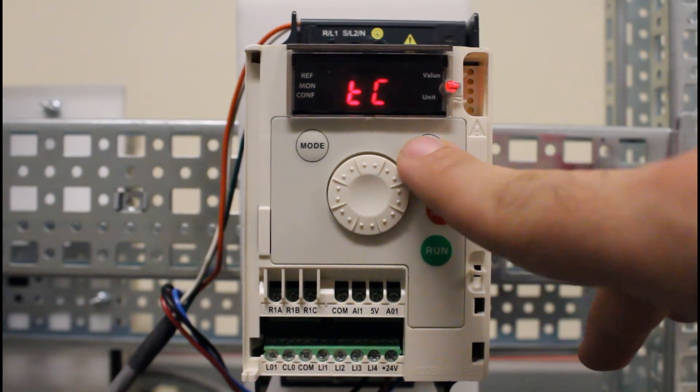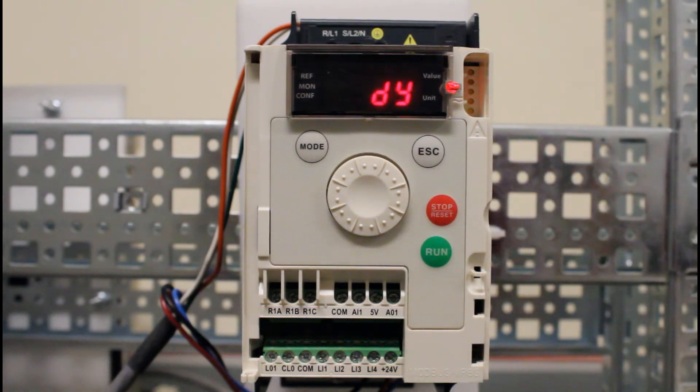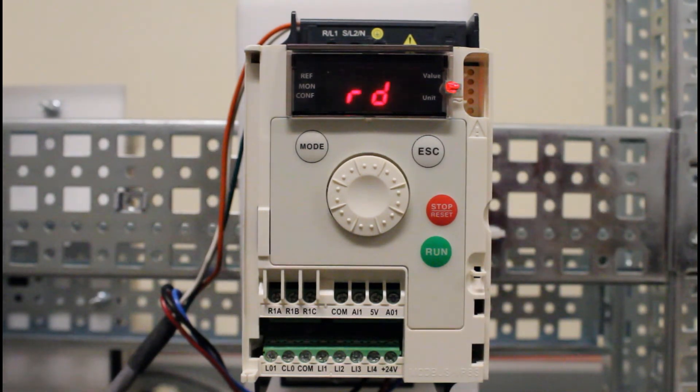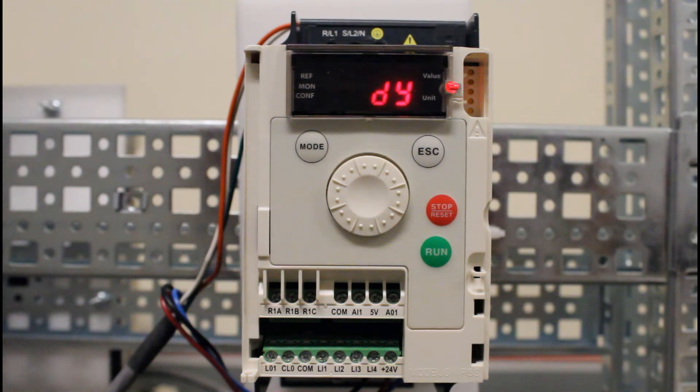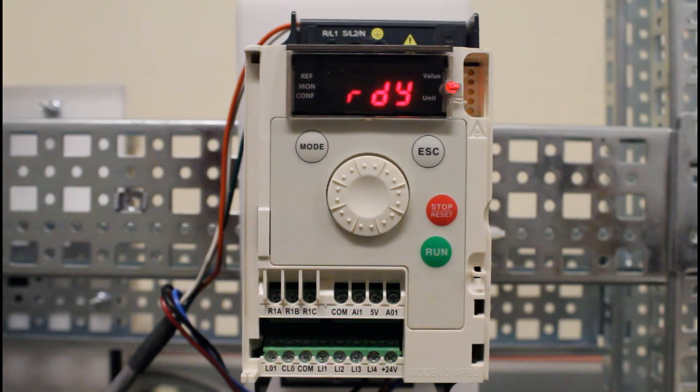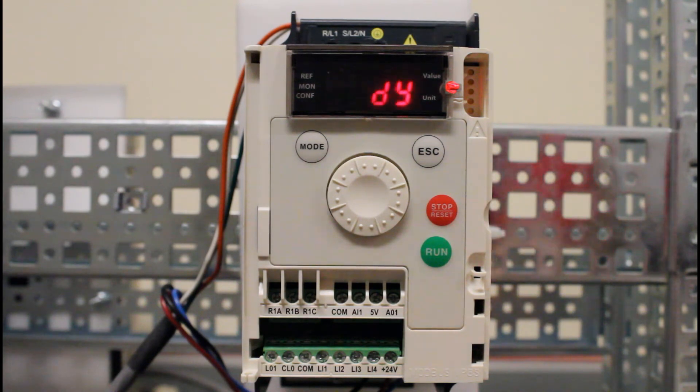And now that's basically it. We have enabled the automatic restart function ATR parameter, and then we set the two-wire type to level.